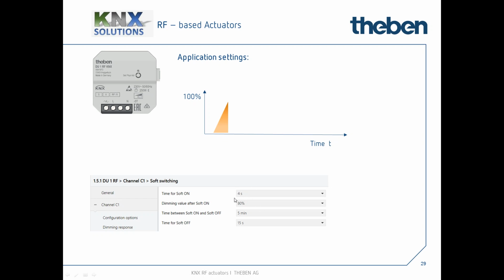We can adjust within 4 seconds, the dimmer runs up to a predefined value, in this case to 80%. Then as long as a presence sensor in the corridor gives a trigger to the dimmer, the light remains on. This is the delay time. If nobody's there anymore, the delay time elapses, and after 5 minutes - quite long here - we have a slight fading out of the light over 15 seconds. The dimmer runs down slowly, giving me an indication if I'm somewhere in a corner not detected by the presence sensor, so I should move or hurry up out of the area.